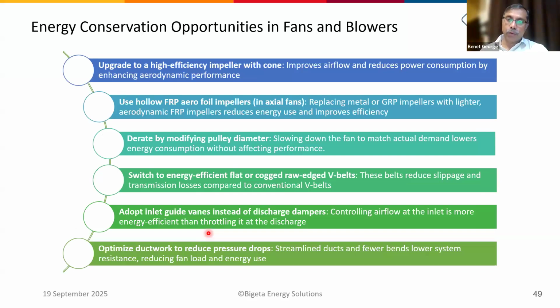Upgrade to a high efficiency impeller with cone. In some cases we need to only replace the impeller. We can use the existing casing, which will reduce the investment. Then use hollow FRP aerofoil impellers in axial fans, which reduce the energy consumption compared to metal fans. Then one option is, if the flow requirement is low, you can even change the pulley and downsize the fan. So if it is a one-time reduction, you can change the pulley size and downsize the capacity, which will reduce the energy consumption. The same affinity law will work. When you reduce the speed by 10%, the power reduction follows the cube of the speed ratio.